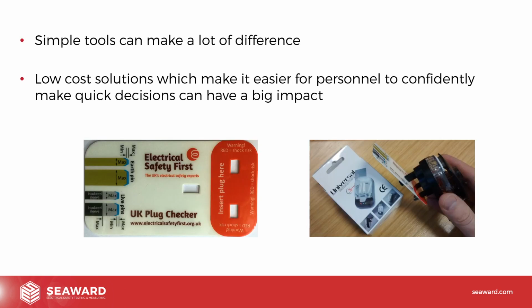Simple tools can make a lot of difference. So a low-cost solution which makes it easier for personnel to confidently make quick decisions can have a big impact. So again, this is an example of the Electrical Safety First plug check card. And if you haven't seen these or you haven't got one, I'd recommend that you get hold of one. They're a useful device. Effectively, they're laid out in line with the British standard, so in line with BS 1363. So the spacing of the pins, the size of the pins, the red zone actually denotes the area where the shock risk is. So that's the area that you shouldn't be able to touch.